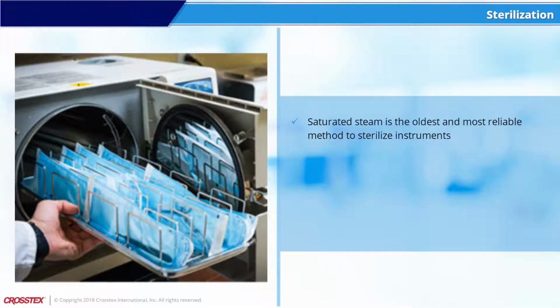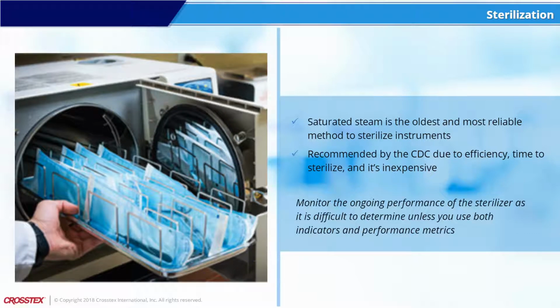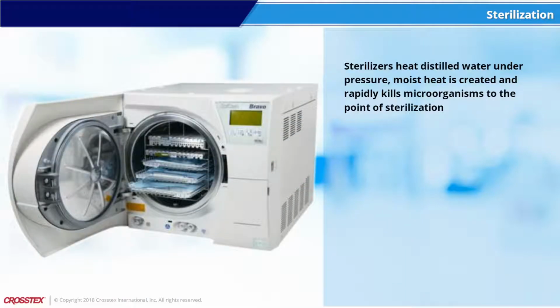Sterilization. Saturated steam under pressure is one of the oldest and reliable methods used to sterilize medical instruments. The CDC recommends steam sterilization as the process of choice because it is efficient, fast, and inexpensive. It is important to monitor the ongoing performance of the sterilizer, as it is difficult to determine unless you use both indicators and performance metrics. Sterilizers heat distilled water under pressure. Moist heat is created and rapidly kills microorganisms to the point of sterilization.